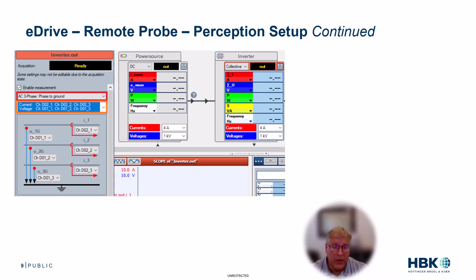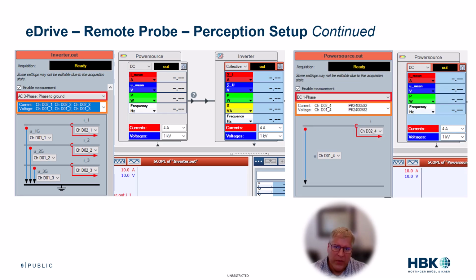Well, now I enable and select the eDrive sheet, then double-click on the inverter element so I can select the appropriate channels for the inverter. Now, in this case, I select D02_123 for the current and D01_123 for the voltage. And in this example, I've decided to use the AC phase to ground connection for the measurement. Then I double-click on the power source element so I can select the appropriate channels for the power source. In this case, that's D02_4 for the current and D01_4 for the voltage. And I've selected the DC 1-phase connection for the measurement.